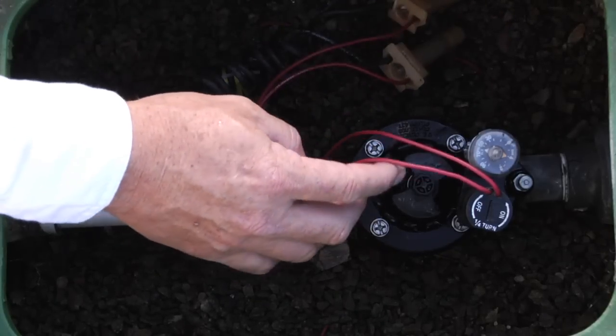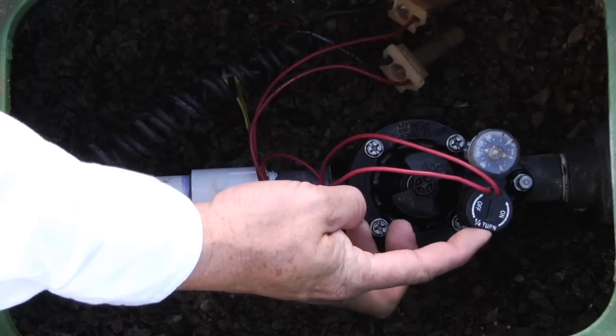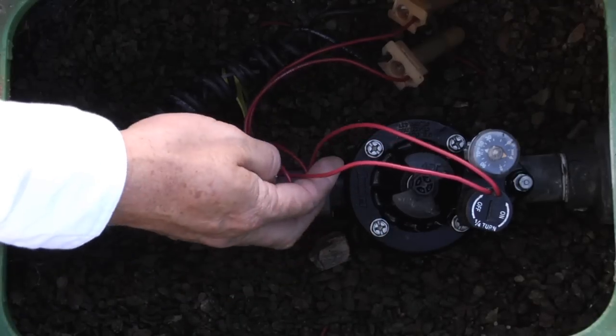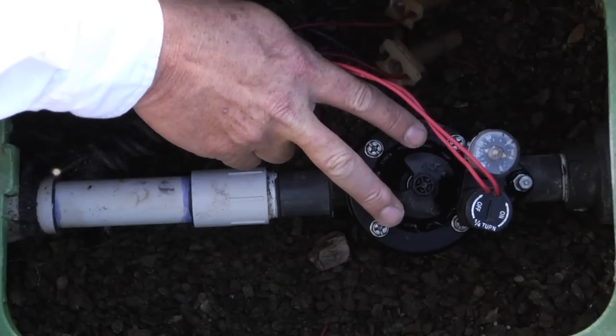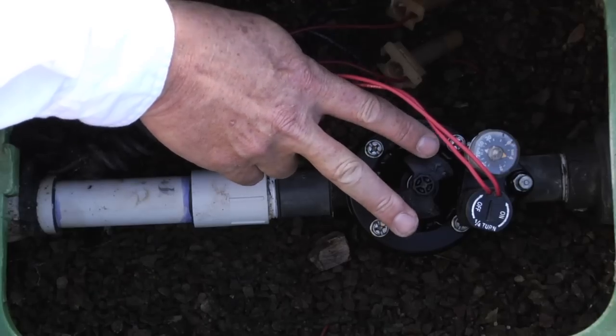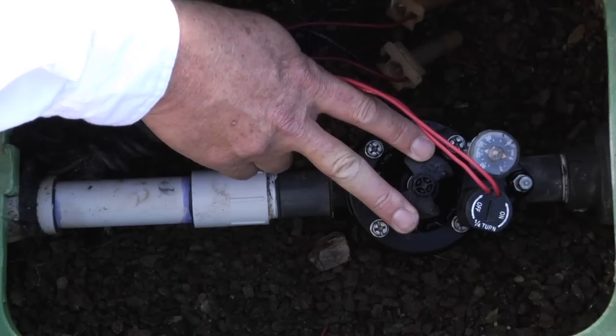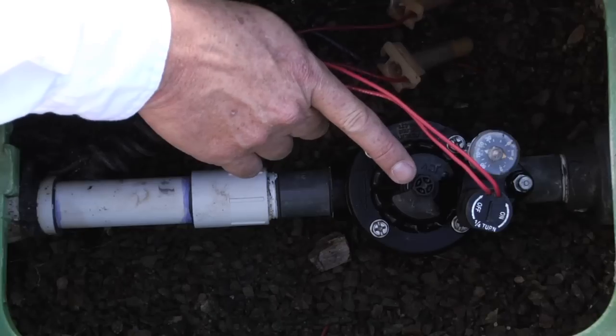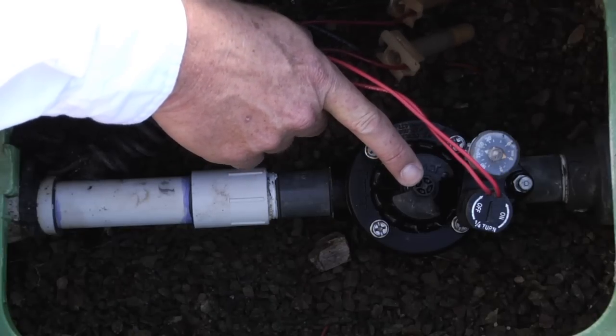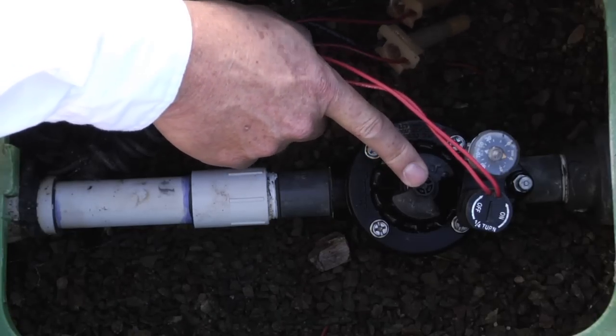The wiring leads over here to the solenoid, which is what electrically actuates the valve. In the middle we have the flow control handle, which regulates the amount of water that passes through the valve when the valve opens. In the center of that we have the manual bleeder screw that will manually actuate the valve.